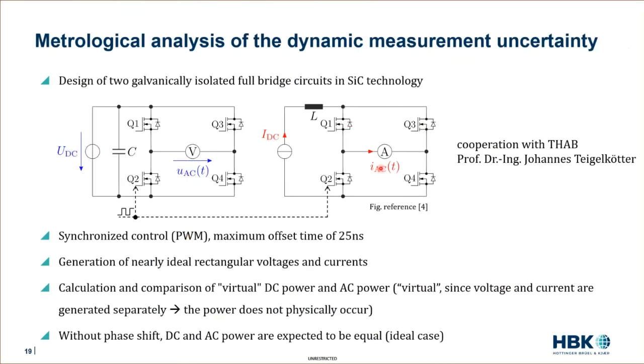You can see that if we take a look at some measurement examples. These have been measured with an oscilloscope to show how good the rectangular waveform is. You see the scale here, the rise time is approximately 50 nanoseconds, which is very suitable to compare power meters with sampling frequencies ranging from 1 megahertz to 10 megahertz.